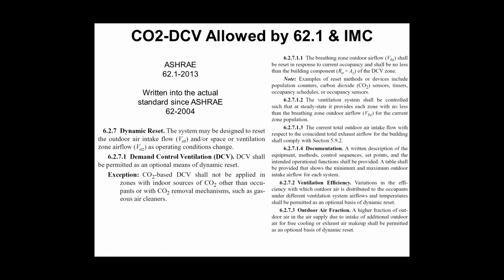The mechanical code in ASHRAE 62 specifically allows CO2-based demand control ventilation, and they have done so for over a decade. It spells it out by name in the code language. So you can do this. You can throttle back the outside air level when people are not there and breathing, and the CO2 sensor is an indicator of who's breathing.